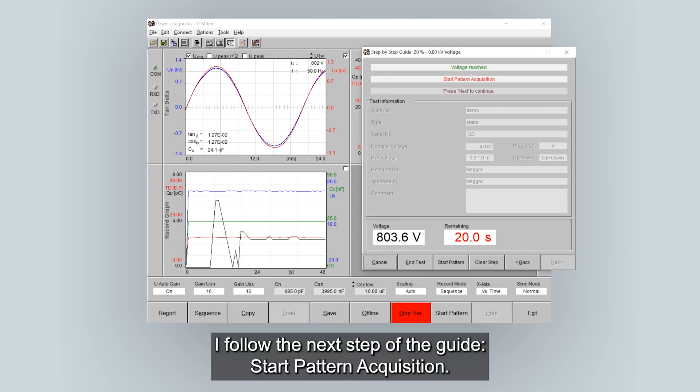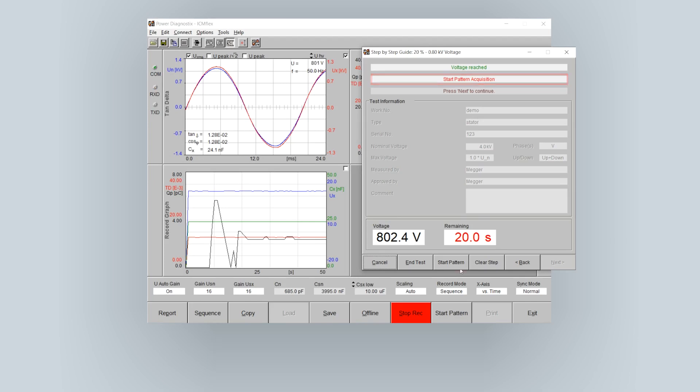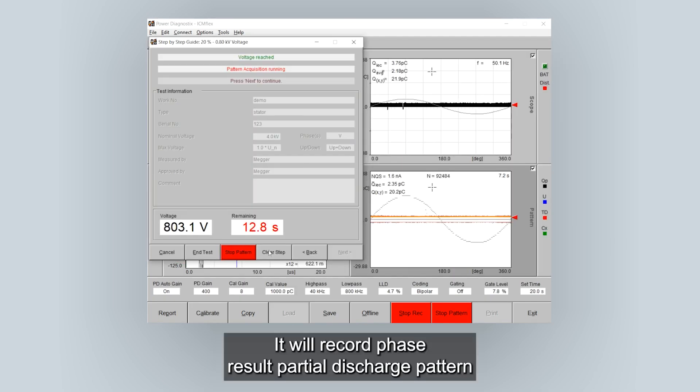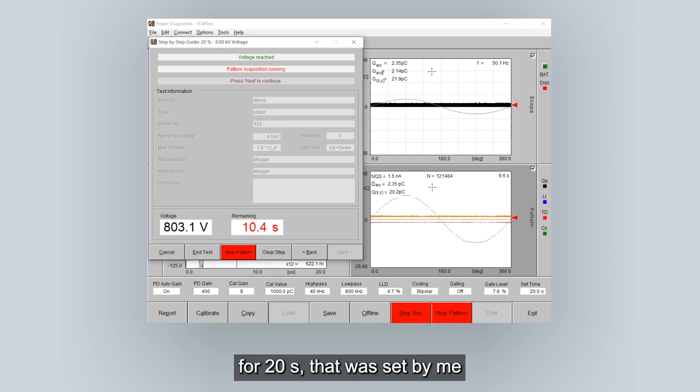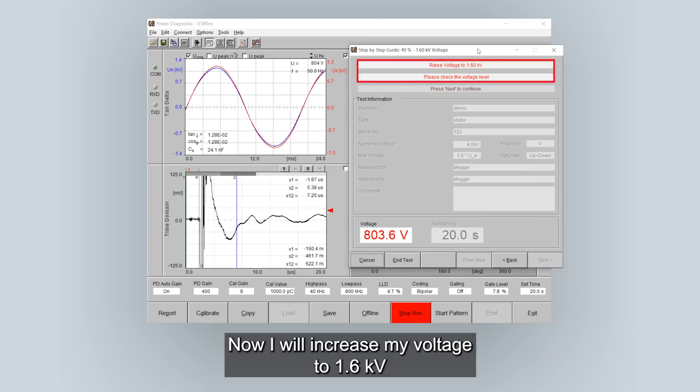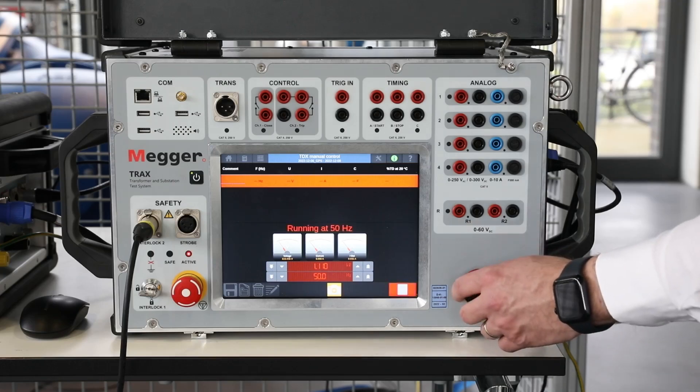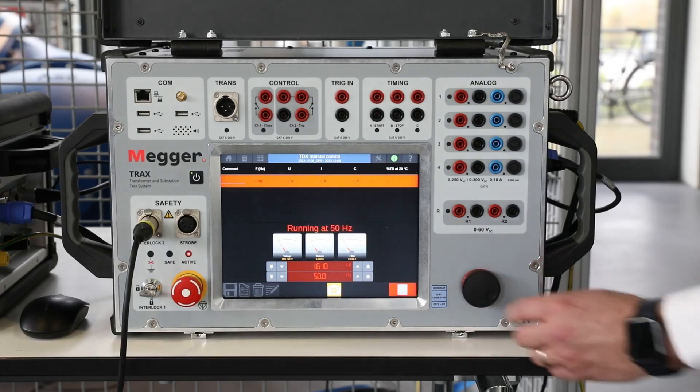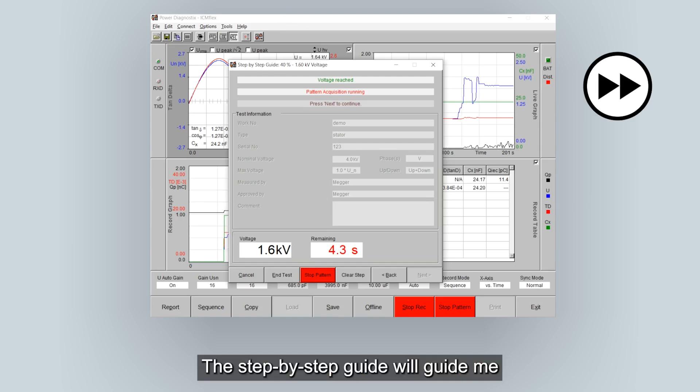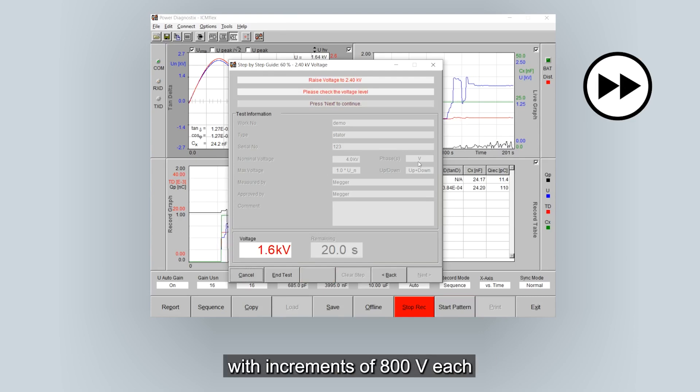I follow the next step of the guide. Start pattern acquisition. It will record phase result partial discharge pattern for 20 seconds. That was set by me initially. Press next to continue. Raise voltage to 1.6 kV. Now I will increase my voltage to 1.6 kV using my Trax.